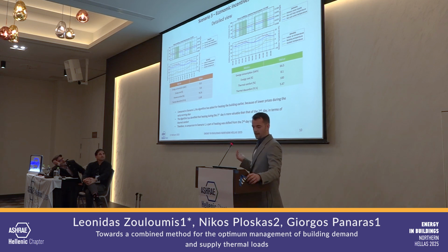would be a conventional thermal system at the moment, and compare it to the respective of scenario 1, we can see that the algorithm has opted for heating the building earlier because of lower prices during the early morning days. And moreover, the algorithm has identified that heating during the first day is more valuable than that of the second day in terms of thermal comfort.